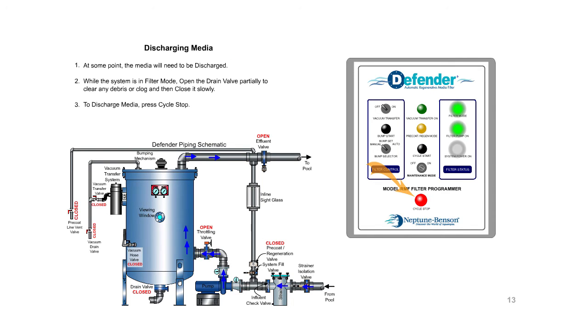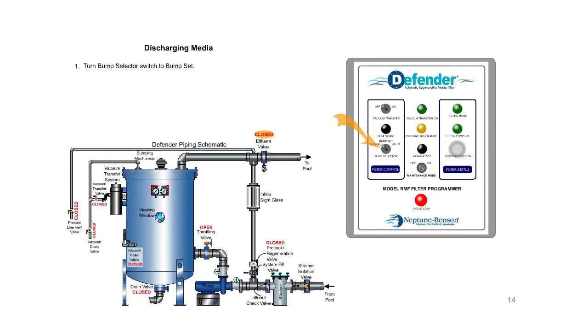Discharging media. At some point, the media will need to be discharged. While the system is in filter mode, open the drain valve partially to clear any debris or clog and then close it slowly. To discharge media, press cycle stop. Turn bump selector switch to bump set. Bump the filter approximately 5 to 10 times by pressing bump start.